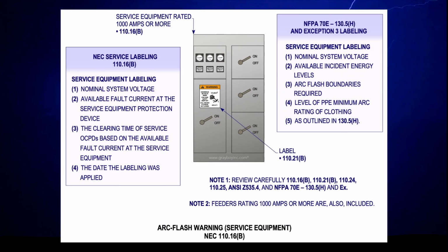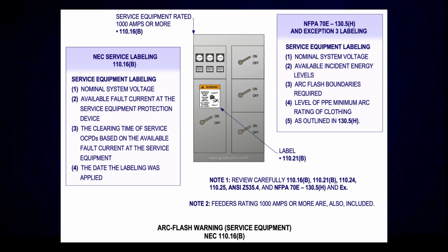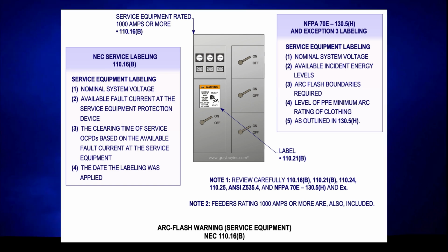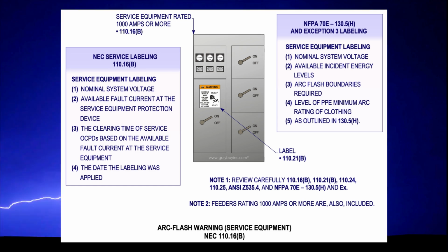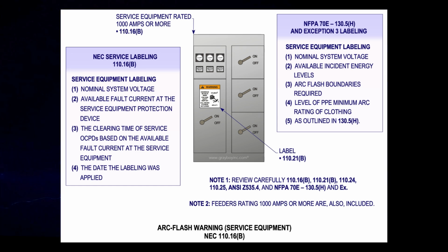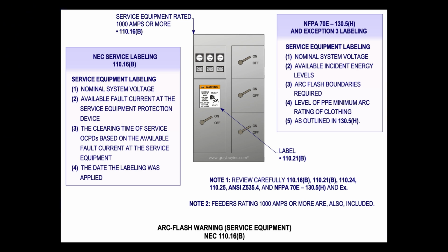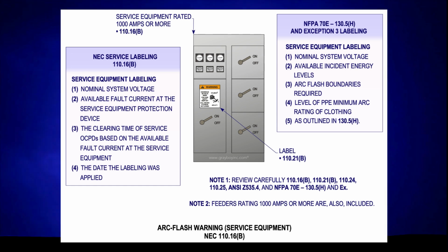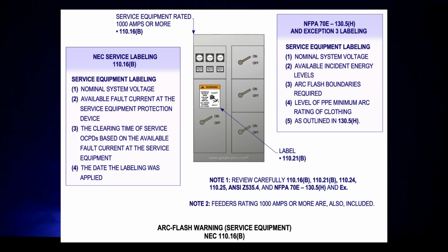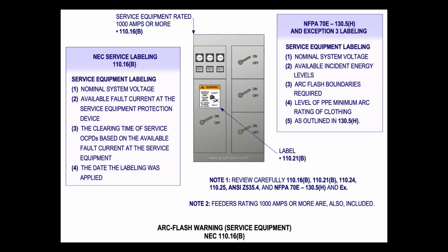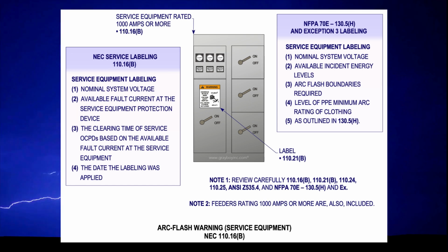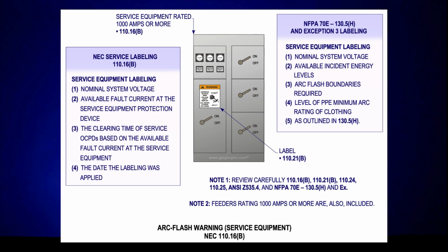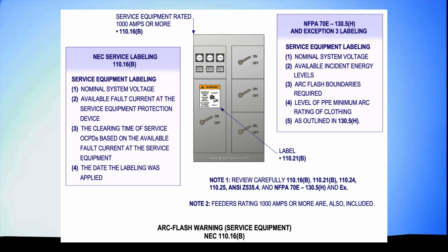A revision has been made to clarify that the requirements in 110.16(B) apply to both service equipment and feeder supplied equipment rated 1000 amps or more in other than dwelling units. The revision from 1200 amps to 1000 amps increases worker safety. A new sentence was added to clarify that the arc flash label shall be in accordance with applicable industry practice and include the date the label was applied.